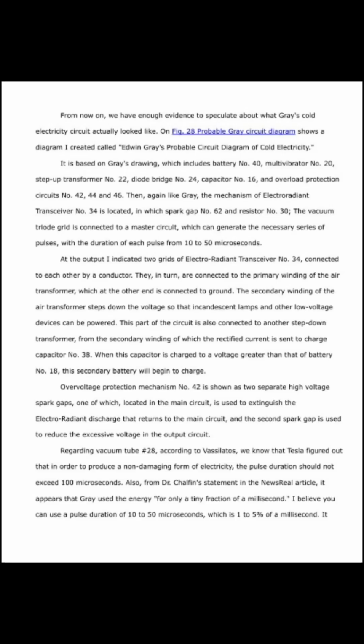Overvoltage protection mechanism number 42 is shown as two separate high-voltage spark gaps, one of which, located in the main circuit, is used to extinguish the electro-radiant discharge that returns to the main circuit, and the second spark gap is used to reduce the excessive voltage in the output circuit.